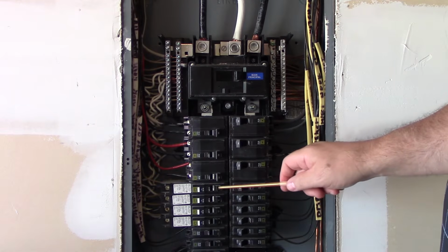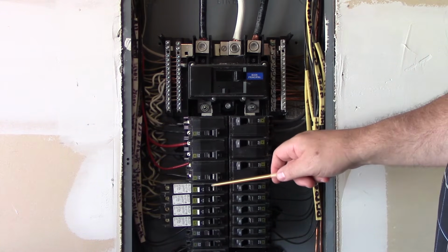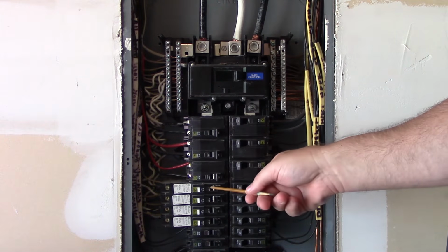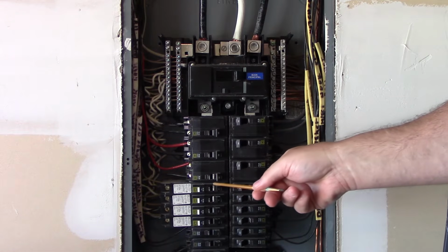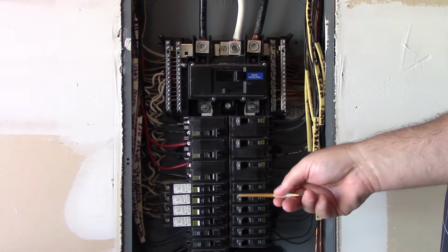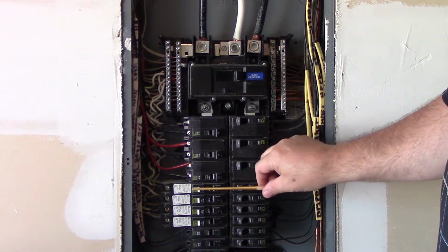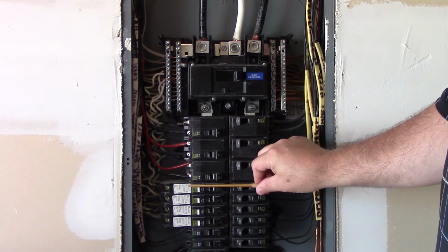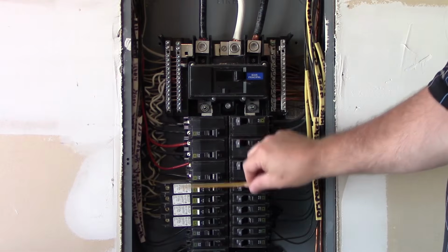But let's go down to here. Let's say that I installed a multi-wire branch circuit, but I installed it improperly. So I put one breaker here for the red conductor, and I put the other breaker for the black conductor over here. Again, that is on the same phase. That is on the same leg. That might be all A.